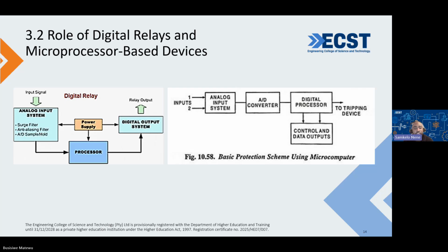Another avenue can be microprocessor-based devices, which function the same way as a digital relay, because they take the analog input and convert it to digital processing. It processes digitally, then sends the output to the tripping device.